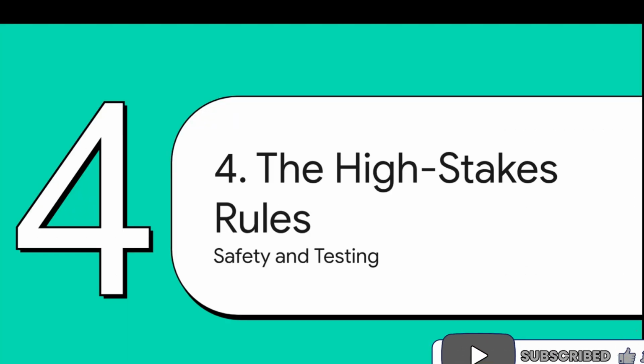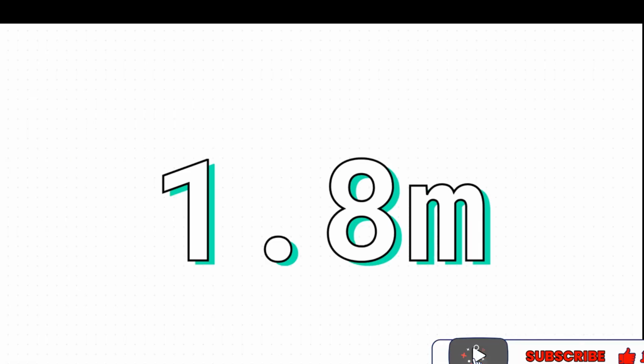Let's get into section 4, what I call the high stakes rules. This is the stuff that prevents catastrophic failures, keeps people safe, and gets the most attention during any kind of inspection or interview. Pay close attention here. 1.8 meters, memorize this number. What is it? This is the absolute minimum distance you need between two separate parallel power lines that are feeding critical equipment. Why? It's simple. This spacing makes sure that one guy with a backhoe can't accidentally take out both your main power and your backup power in one go.